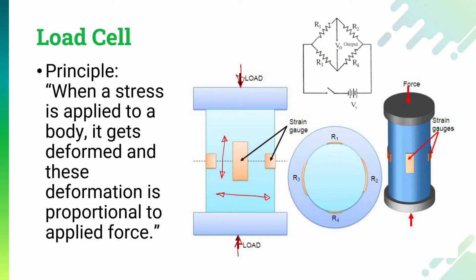Now over here the strain gauges R1 and R4, which are available vertically, are basically along the direction of the applied load. Whatever load I apply, the strain gauge will directly absorb that particular load because they are along the direction. And R2 and R3, these 2 strain gauges, are attached in a circumferential manner. You can observe that they are available in a circumferential manner. So basically they are at right angles to the strain gauges R1 and R4.